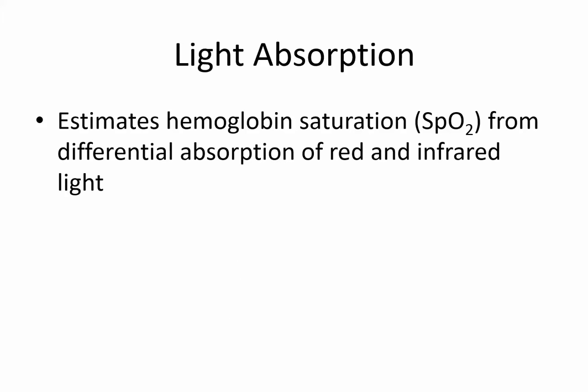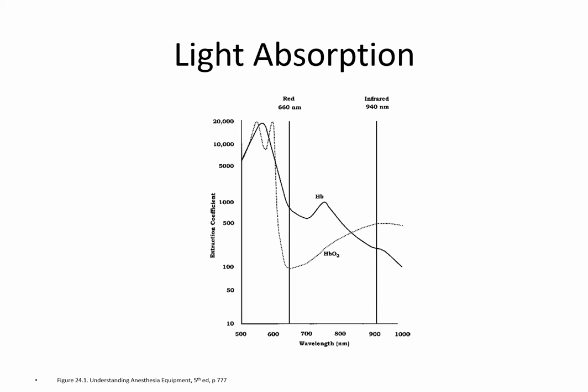As you know, pulse oximetry estimates the hemoglobin saturation from the differential absorption of red and infrared light. This graph shows the relationship between light absorption of oxygenated hemoglobin and non-oxygenated hemoglobin at red and at infrared, and the ability to separate those two, to distinguish those two, is what characterizes the ability of the pulse oximeter to work.